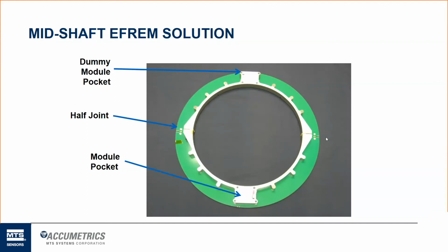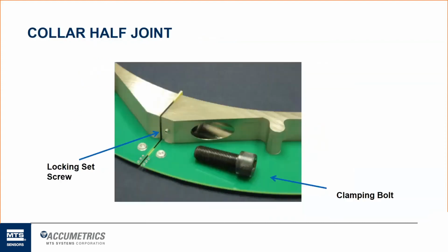As I mentioned earlier, in North America, most power generation machines rotate at 3,600 RPM. Some of the larger machines are 1,800 RPM. So again, speed and diameter are those two critical components that we're going to need in order to accurately design this midshaft solution specific to their exciter. Here's a close-up of how we make that half joint of the collar. Again, it's a high strength bolt that goes through and gets bolted down across that half joint. And then we also provide a locking set screw as another mechanical feature, just to give you or the end user that extra peace of mind that that bolt could never come loose or work its way out.